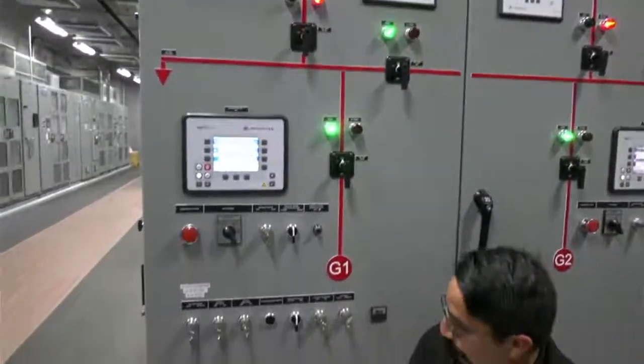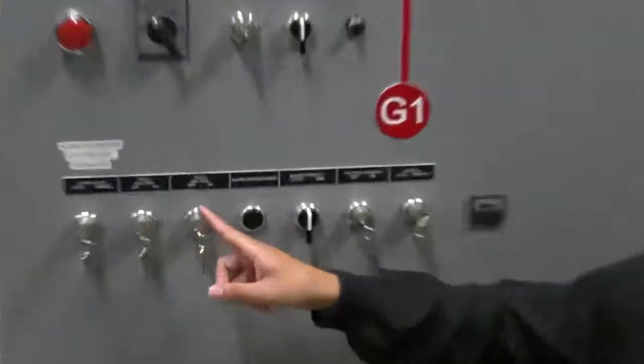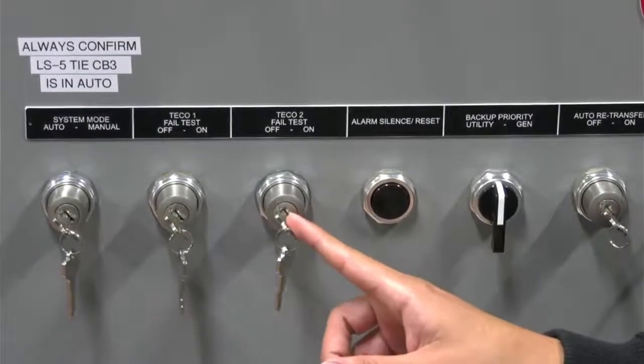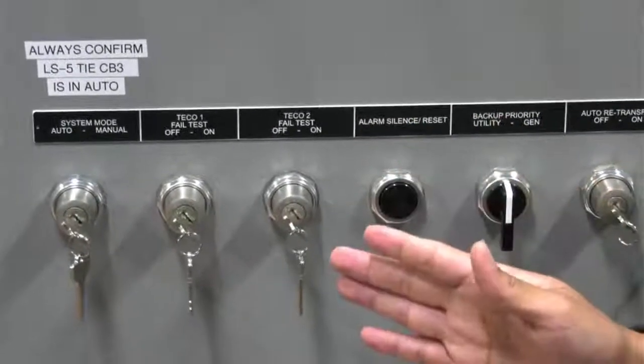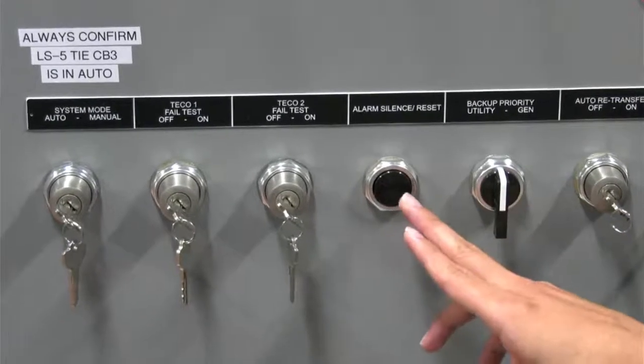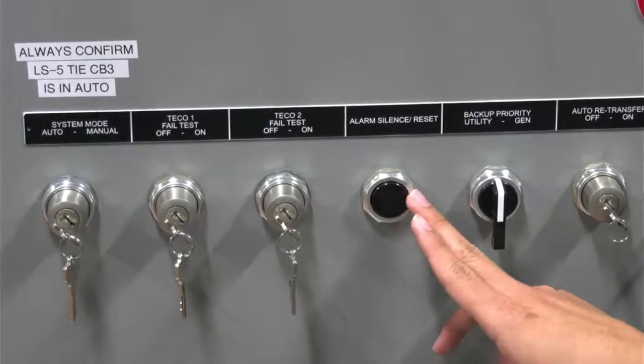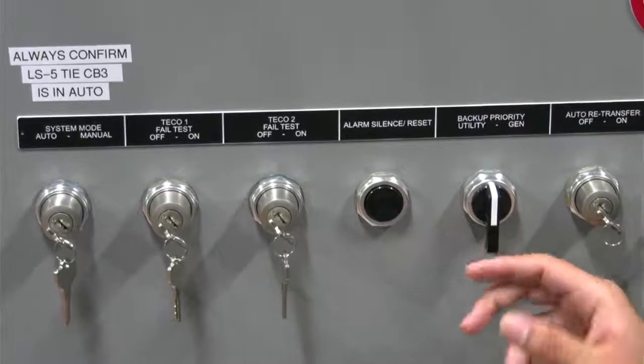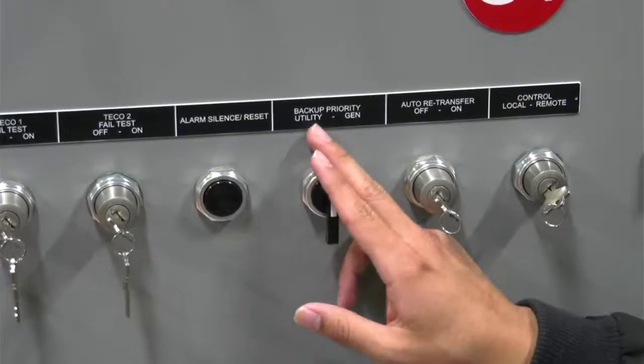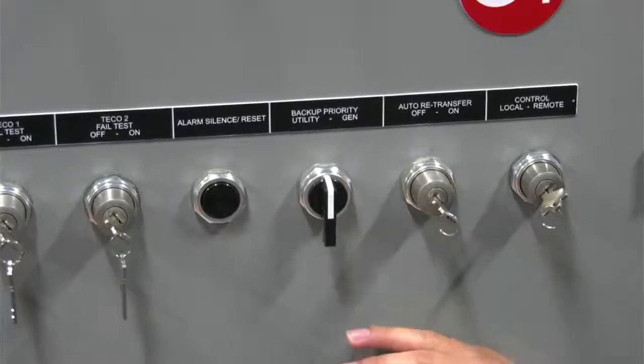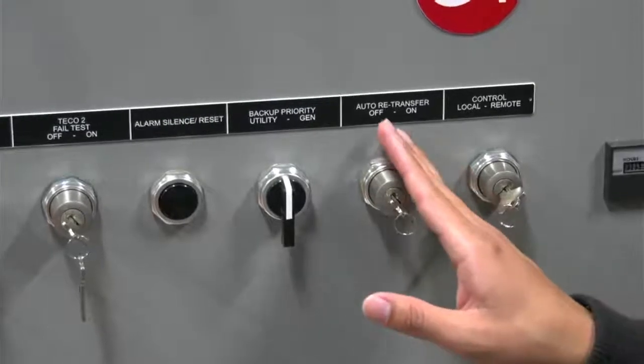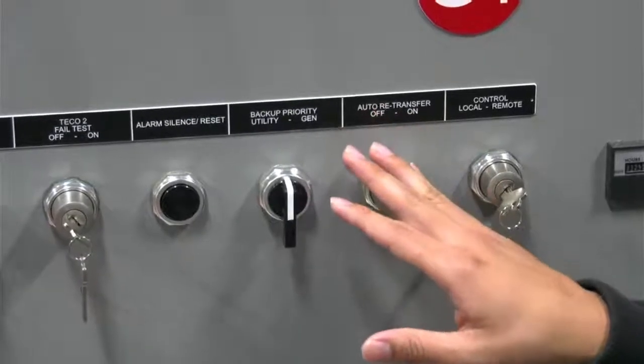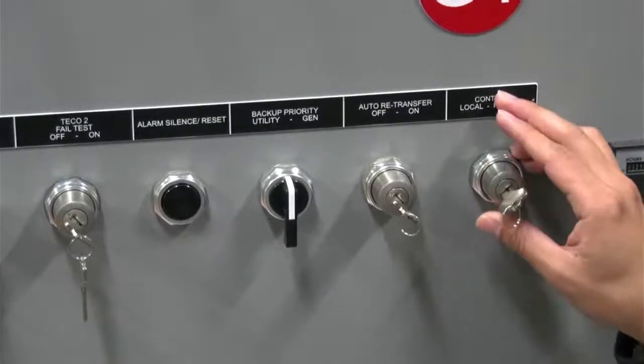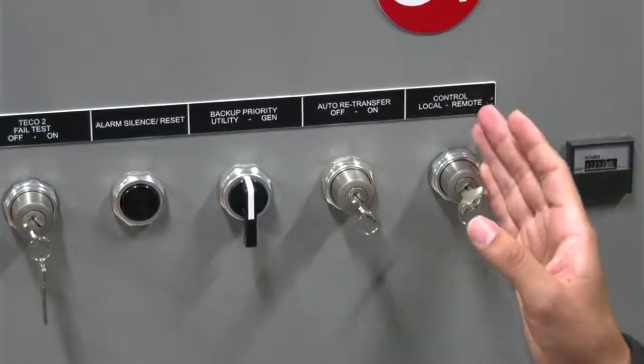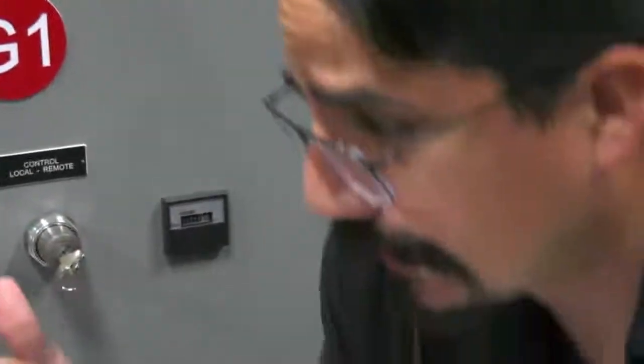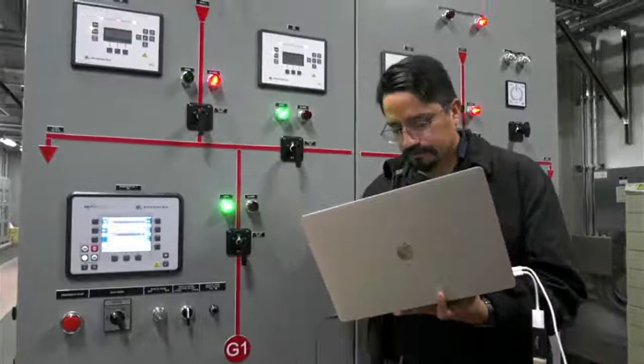Okay, so continuing here, we have the TECO 1 and the TECO 2, so you can do the same for TECO 2. Opening the circuit breaker, going blackout, and backing up with the generators. You can do the reset and silencing of the buzzer with this button. You can change the priorities if you want a priority on utility or generator. I'm going to explain a little bit more about this in a moment. And you can do the auto retransfer off or on. I'm going to explain a little bit about this in a moment. And you can select if the system is going to accept local or remote controls. Remote controls are coming from the SCADA, and the EasyGen is accepting the remote commands, basically.